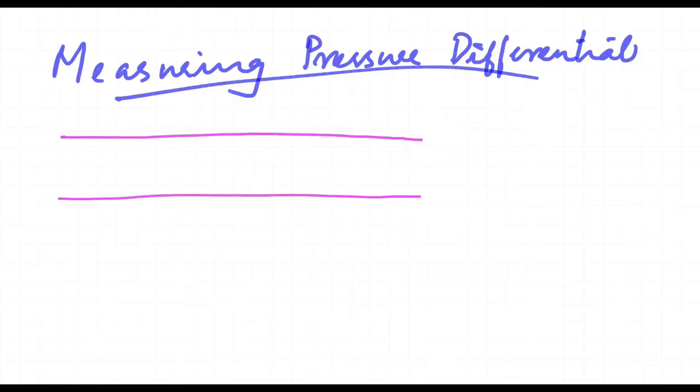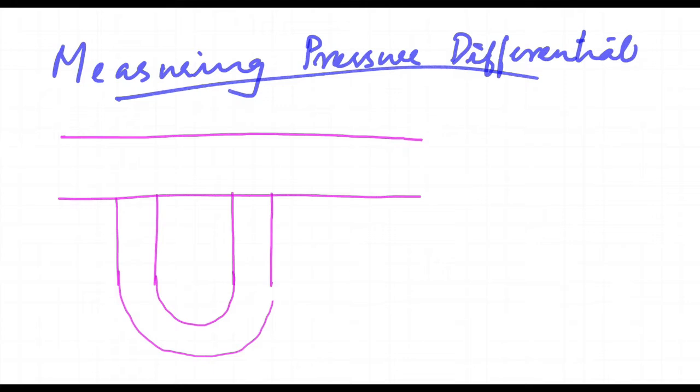Now we are considering a pipe flow with a fluid of, say, density A, and the simple manometer has another fluid filled in it with a different density to the fluid in the pipe. When you make the connection of the manometer, it is important that the connections are perpendicular to the pipe, otherwise the pressure measurement will not be correct.